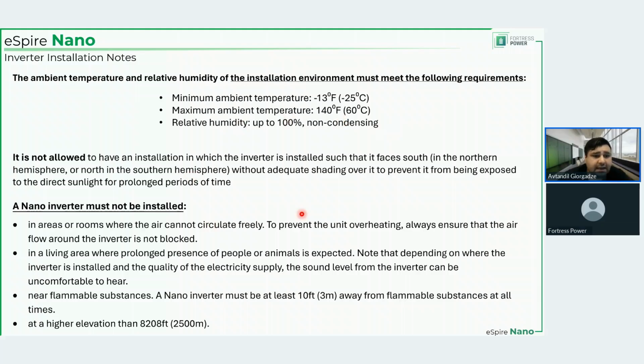to 100%. It is not allowed to have an installation in which the inverter is installed such that it faces south. So this would be applicable in the northern hemisphere. In the southern hemisphere, the inverter must not be facing north. You can have it facing south in the northern hemisphere or facing north in the southern hemisphere, but only if you have adequate shading over it, because this rule is motivated by the fact that we don't want the inverter sitting in the face of the sun, exposed to direct sunlight for prolonged periods of time, because that could damage the screen on the inverter. Cooling of the inverter will become much more difficult than otherwise. So that's the motivation behind this rule.